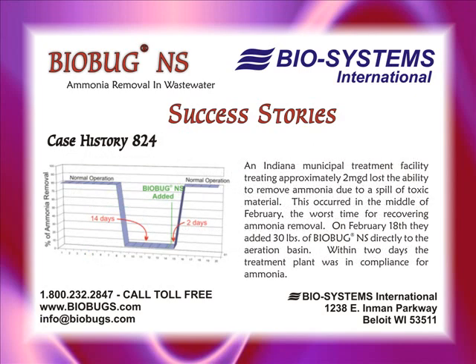An Indiana municipal treatment facility treating approximately 2 MGD lost the ability to remove ammonia due to a spill of toxic material. This occurred in the middle of February, the worst time for recovering ammonia removal. On February 18th, they added 30 pounds of BioBug NS directly to the aeration basin. Within two days, the treatment plant was in compliance for ammonia.